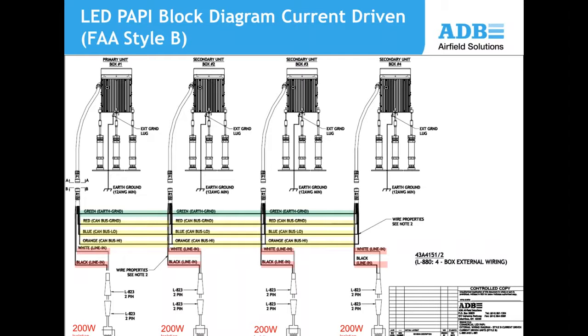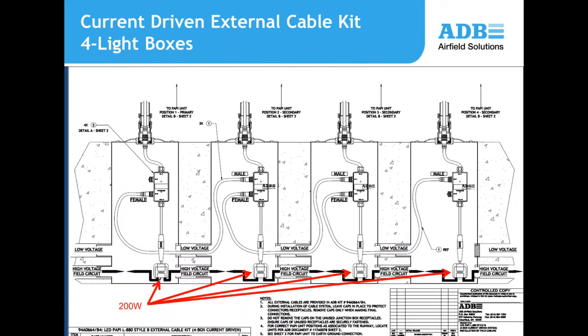For the current-driven PAPI system, cables run between each light unit and each requires a 200-watt isolation transformer to provide the necessary operating current. The isolation transformers are visible inside the base can and are connected to the connection units that are part of each PAPI light unit.